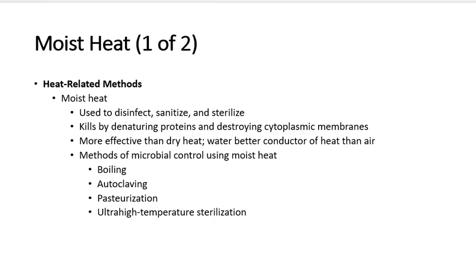That is just high heat at high pressure, and it will sterilize. You will also put in a little control that tells you this is sterile now, because we'll use a strip that's impregnated with organisms that withstand high heat. If they die, then we know the autoclaving has worked.